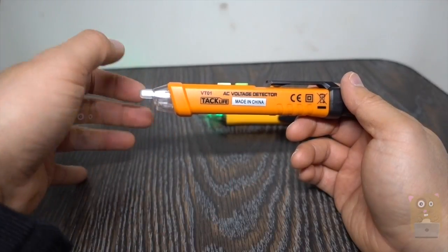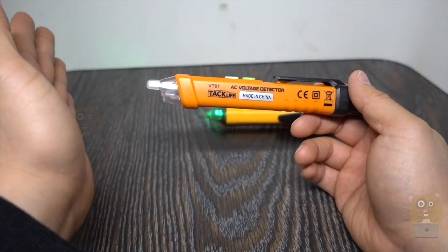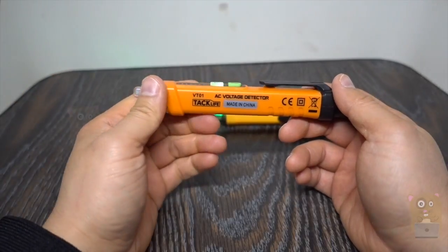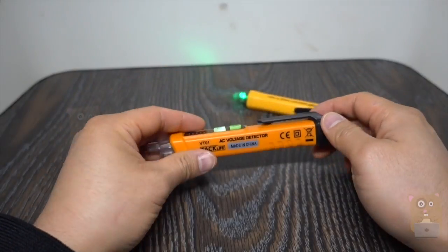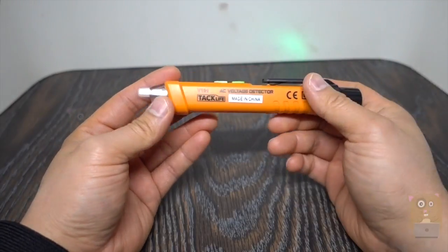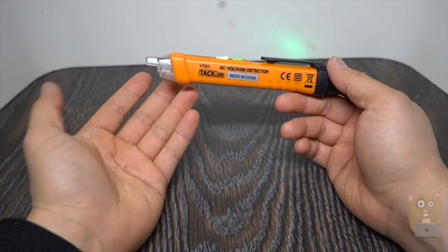Even though this Tacklife voltage detector is just $10, I can't recommend it because it's overly sensitive. Let's say there are three wires and the one on the far left is the one I want to work with — I want to make sure the voltage is off and not flowing through it. Well, with this one I can't rely on the results because it's overly sensitive. Whereas my other one costs significantly more, but at least I don't get any false readings. I need to actually press it and touch it, then it'll read. It's not like this one where I can be a foot or so from the live power source and have it set off. So yeah, with that said, no — I won't recommend this.